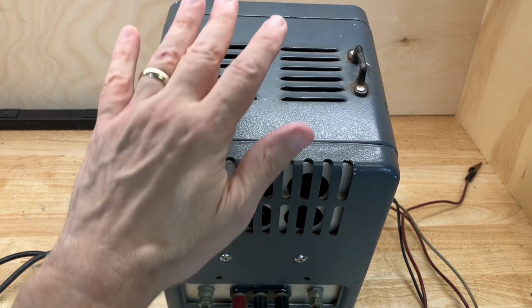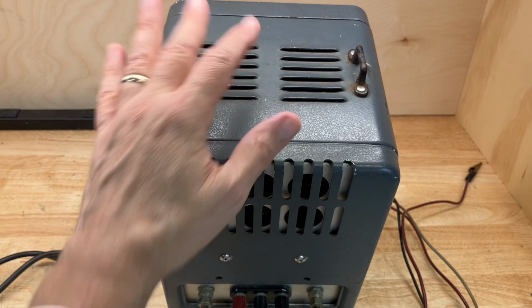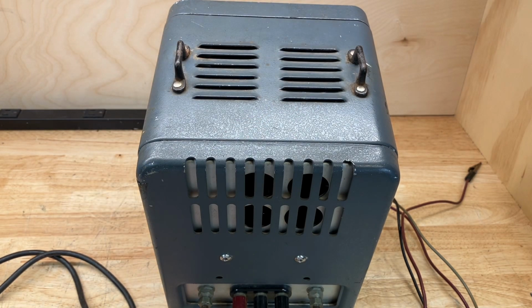So that's the incorrect fuse. I don't dare plug it in and turn it on, because someone has changed the fuse, which means there might be a reason they changed it to the incorrect fuse, like there's a short internally to the instrument or something. We don't want to release any unnecessary smoke before testing this instrument out. So I'm not going to just plug it in and turn it on.